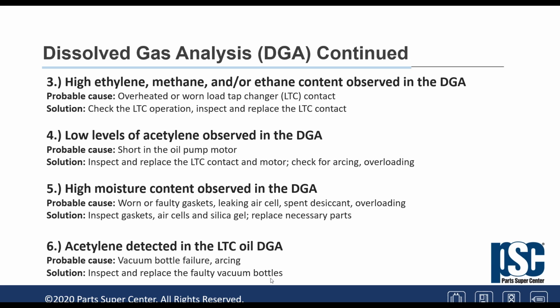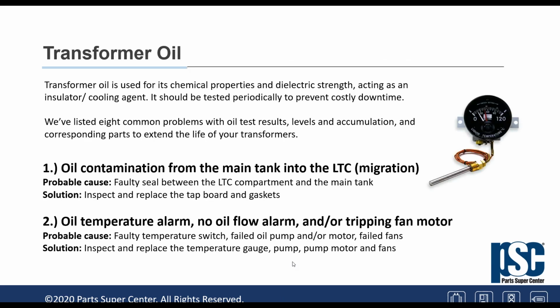Item 6 says acetylene detected by LTC. Again, the probable cause is vacuum bottle failure, because in theory, if it's a vacuum type LTC, load tap changer, there shouldn't be any arcing in the unit. But if the vacuum interrupter is failing, that means the main contact is opening under load, so it is arcing in there. In this case, the acetylene will be detected in the LTC compartment. And if there is some tracking or some crack in the board, then we're going to have this oil migrating from the LTC compartment to the main tank.